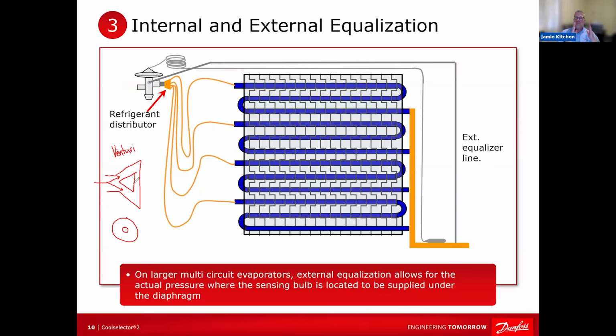So remember, whatever the temperature equivalent of the pressure drop through your distributor is, and through the evaporator, whatever the temperature equivalent of that pressure drop is, you will add that to the superheat opening requirement. So the bigger the pressure drop, the more superheat is going to be required at the sensing bulb to open it. And again, you're always going to underfeed that evaporator.